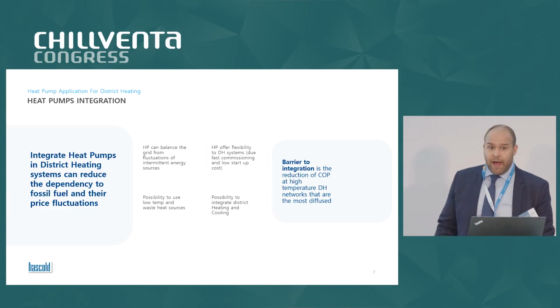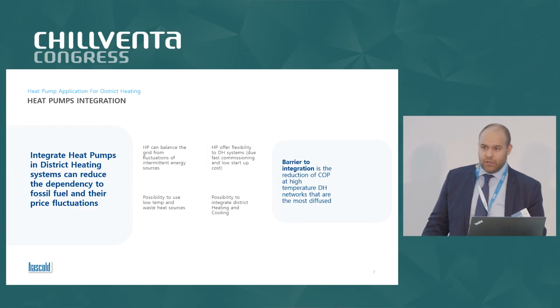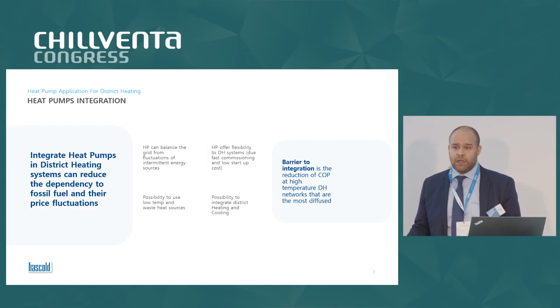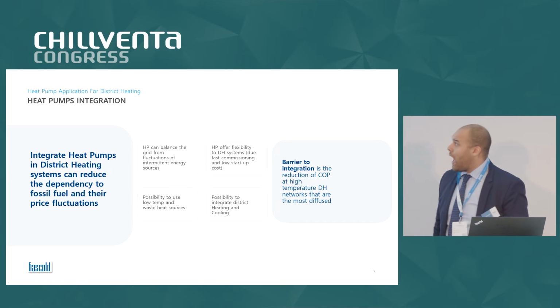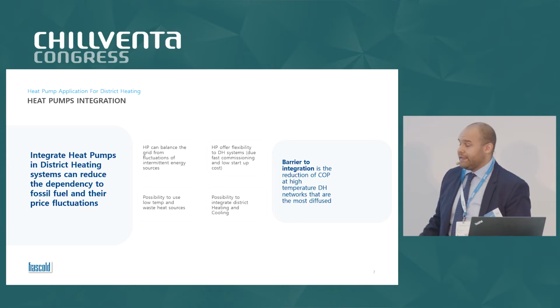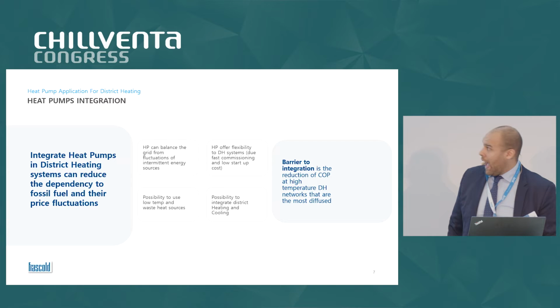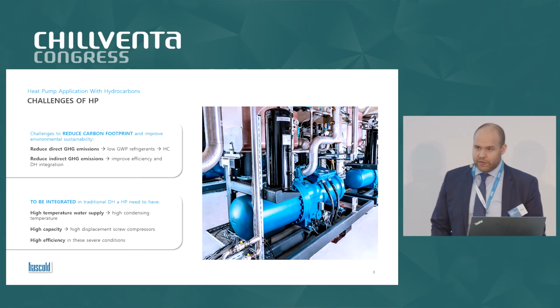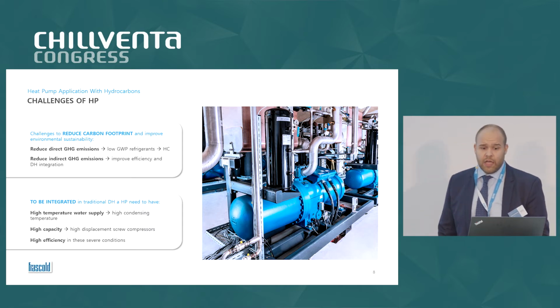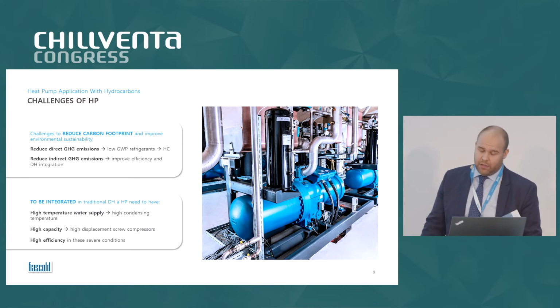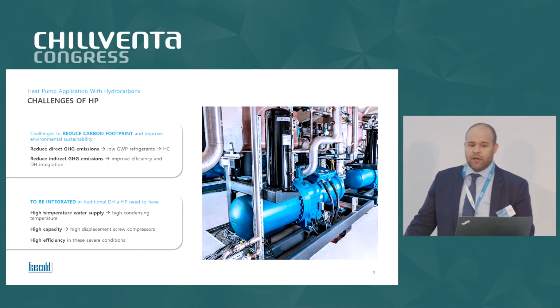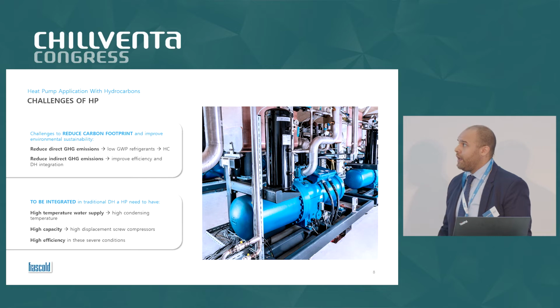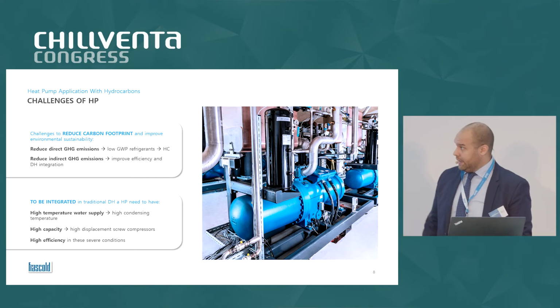The barrier that we can see in the integration at the moment is the fact that most of the district heating systems, the traditional district heating, are at high temperature. So at the moment, there is a necessity to produce high temperature heat pumps, and we'll see later how to do it. The challenges to reduce the carbon footprint in the heating sector and improve environmental sustainability are clearly the reduction of direct greenhouse gas emissions, and the response is clear: use low GWP refrigerants, and in this case we can possibly use hydrocarbons. Then also reduce indirect greenhouse gas emissions, improve the efficiency of the system, and integrate heat pumps in district heating systems.